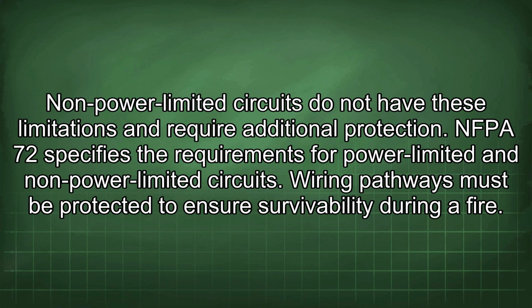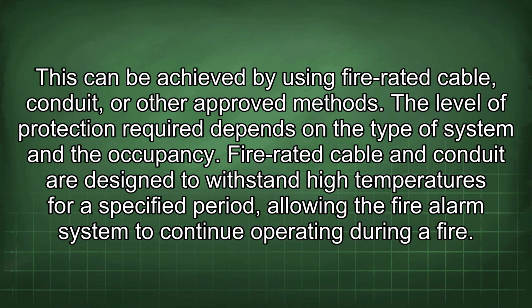Wiring pathways must be protected to ensure survivability during a fire. This can be achieved by using fire-rated cable, conduit, or other approved methods. The level of protection required depends on the type of system and the occupancy. Fire-rated cable and conduit are designed to withstand high temperatures for a specified period, allowing the fire alarm system to continue operating during a fire.